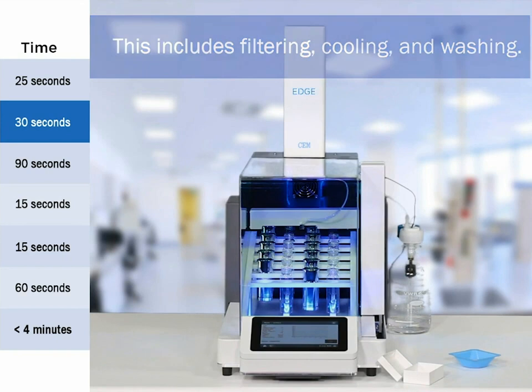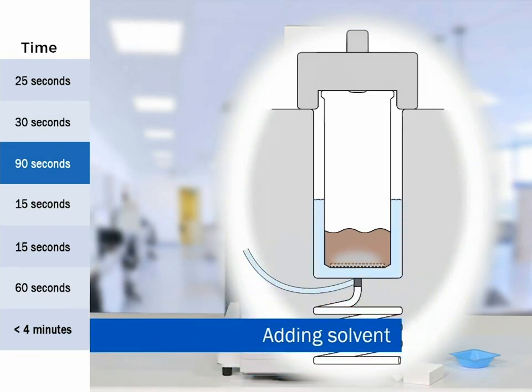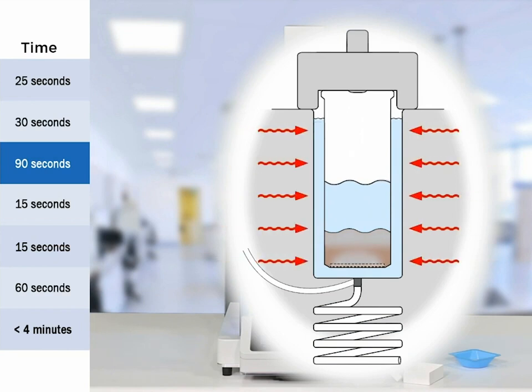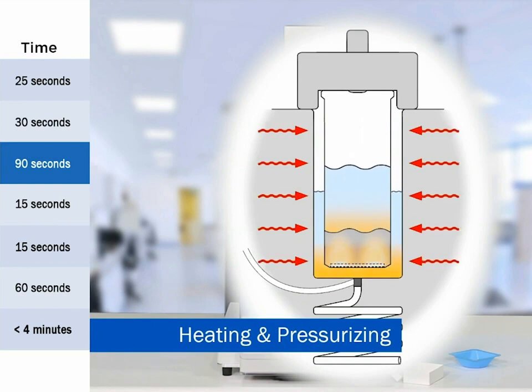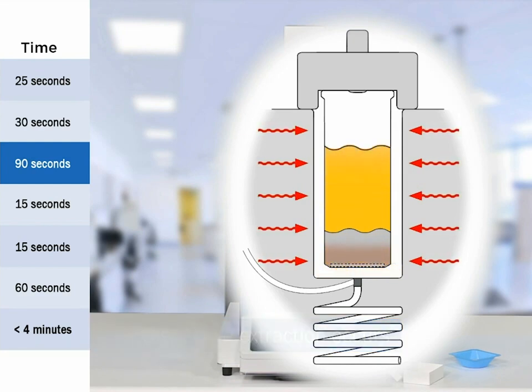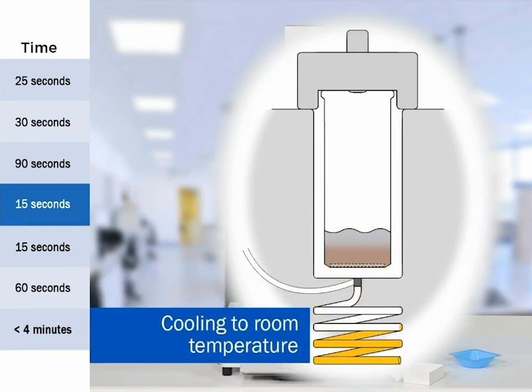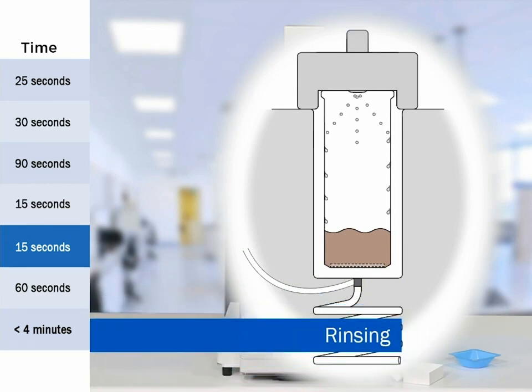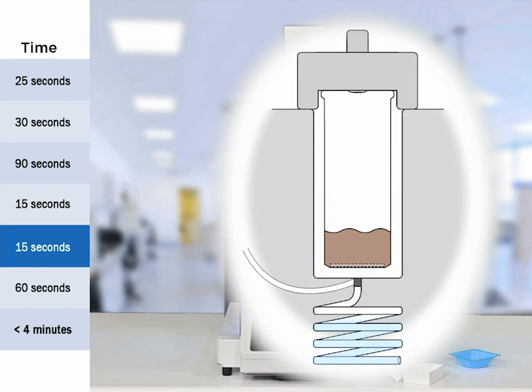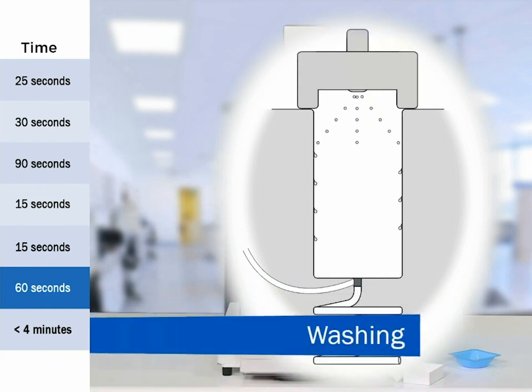The Q-cup is loaded into the chamber, and the pressure seal comes down creating a pressurized environment. This cross-section of the chamber shows that solvent adds from both the bottom and top. The bottom creates solvent on the outside of the cup which, as we heat, disperses up into the sample — creating our dispersive effect and aiding extraction efficiency. Once we reach temperature, we drain. The extract goes through a cooling coil, so your hot extract is at room temperature with no loss of low volatiles. Then a rinse step runs clean solvent through the sample one last time.